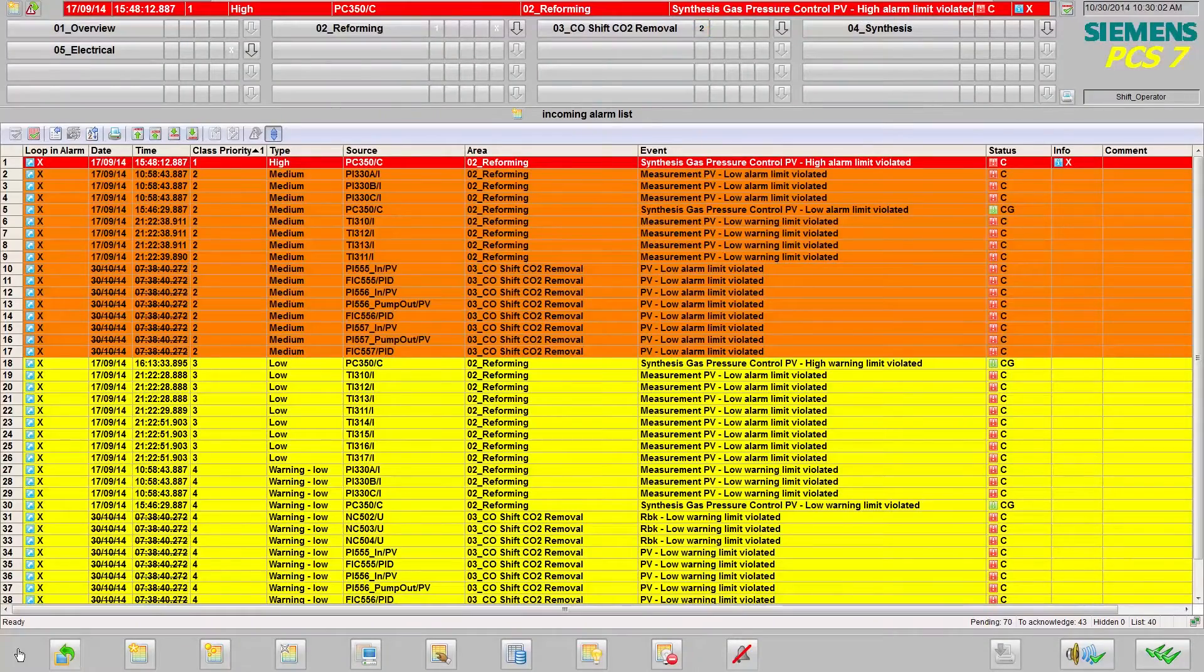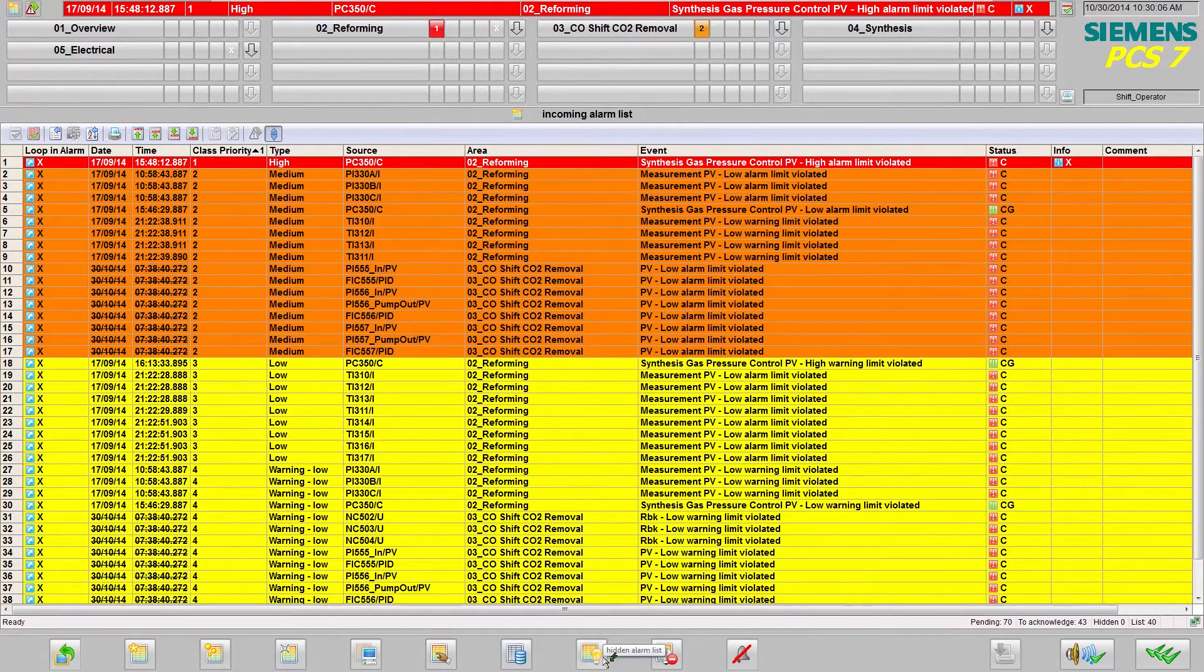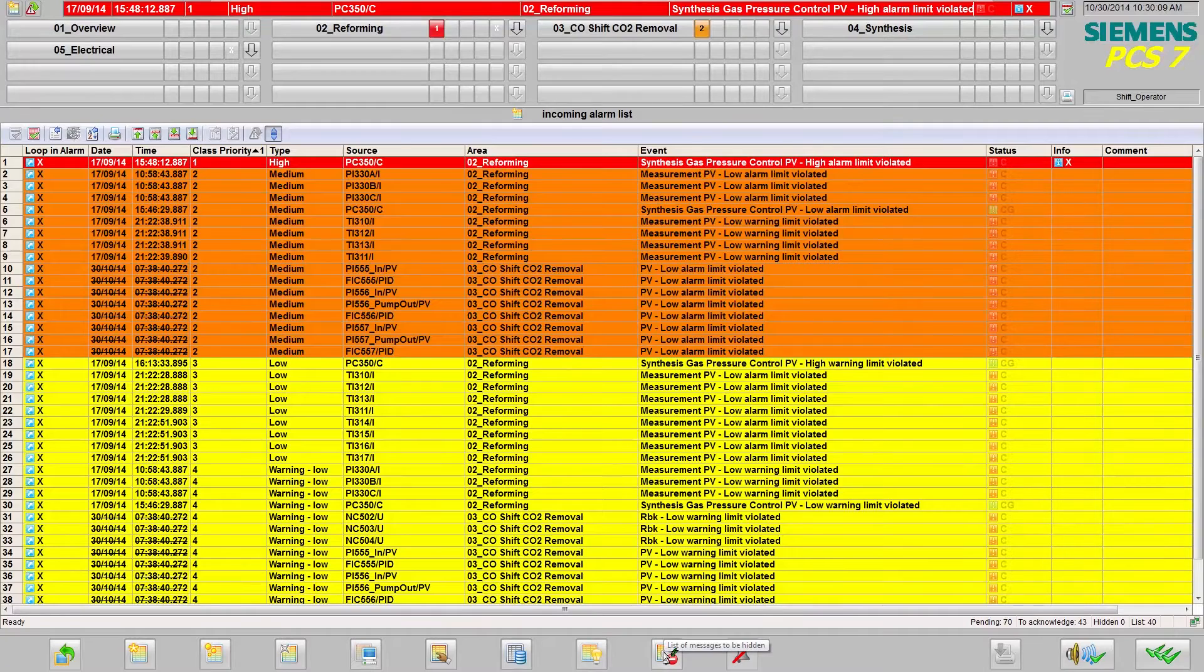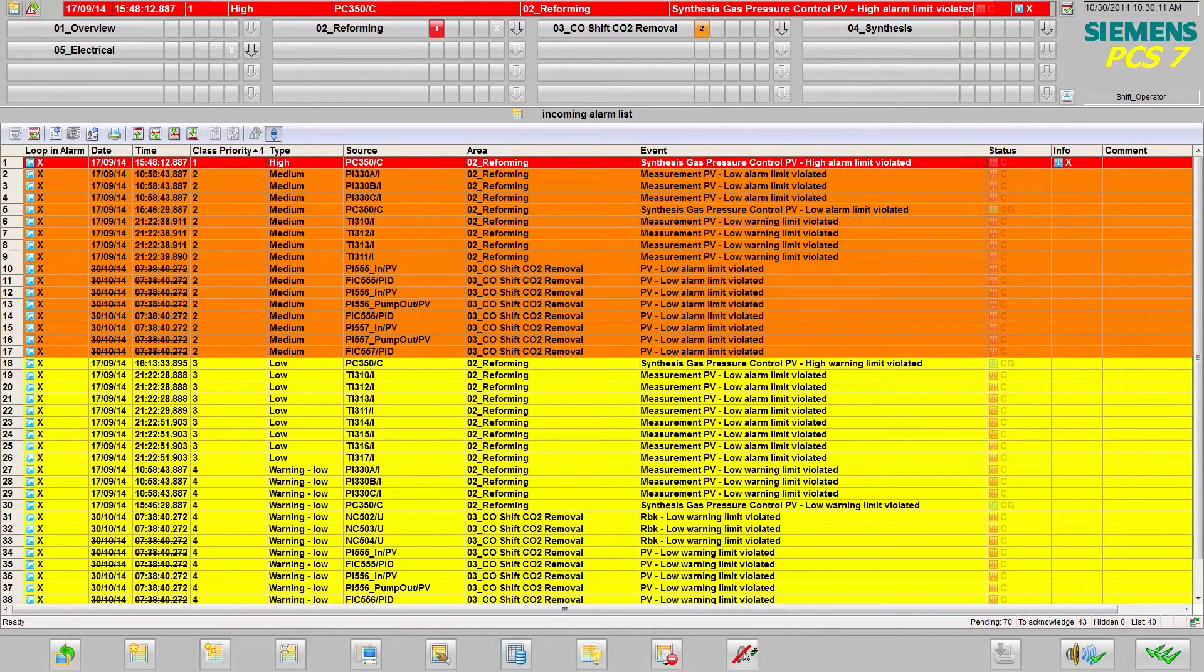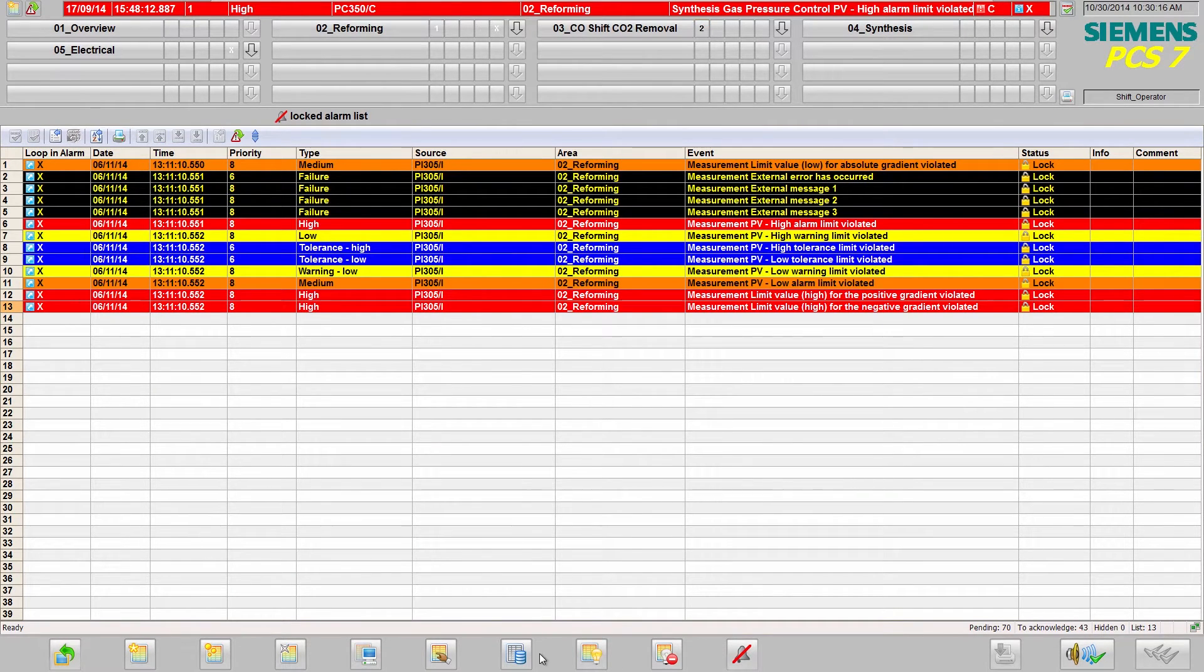you can hide alarms for certain measuring points dependent on the mode of operation of the plant, for example when starting up plant units or during maintenance for a specific duration. The hidden messages are archived in the alarm system.